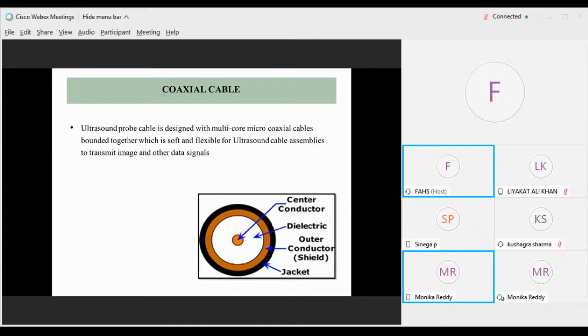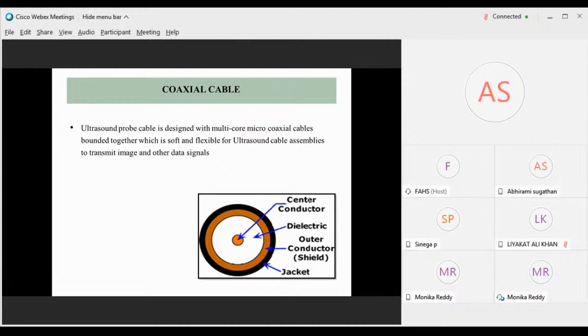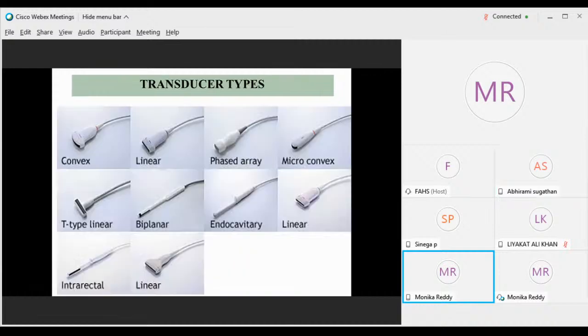So next comes the coaxial cable, which connects the transducer with a cable. It is designed with multi-core and micro-coaxial cables, which are bonded together. In the center you can see the conductor where the signals will be conducted, and the outer one is the jacket. The cabling is properly done, and it should be soft and flexible for ultrasound cable assemblies to transmit the image and to drag it while operating. It should be soft and flexible for easy operation. So these are most of the transducer types. There are so many types based on the shape and the thickness of the crystal. So these transducers are of a varied range of types.